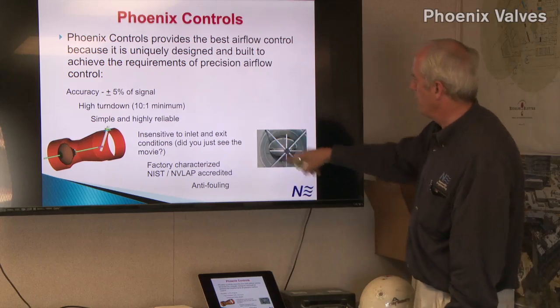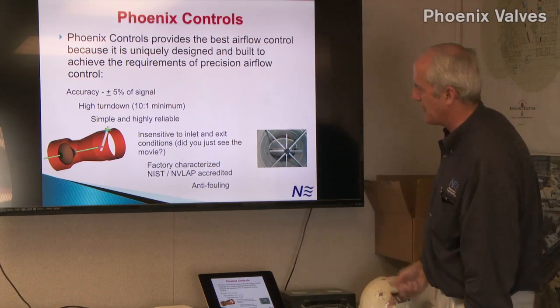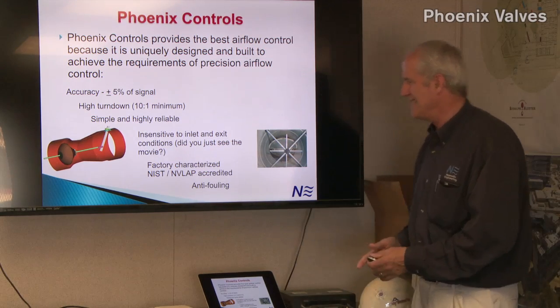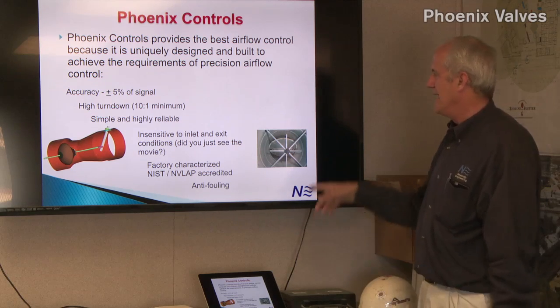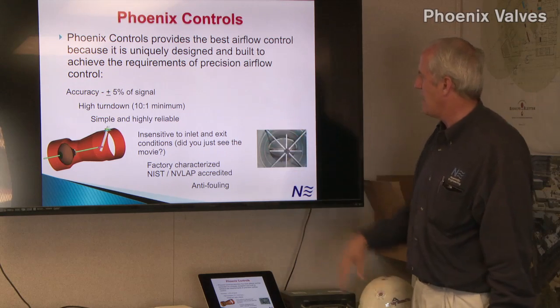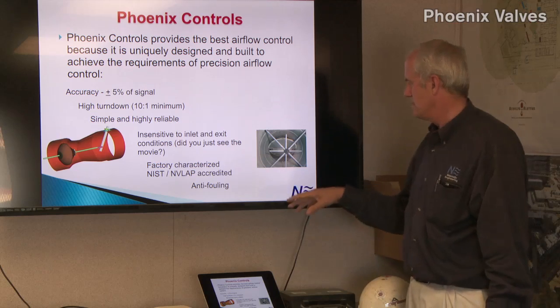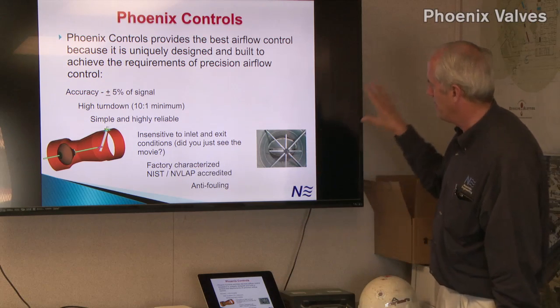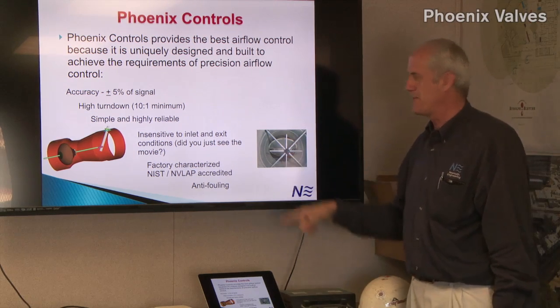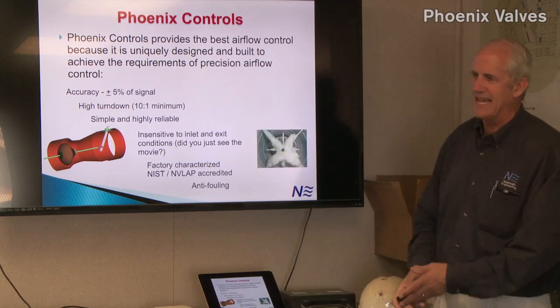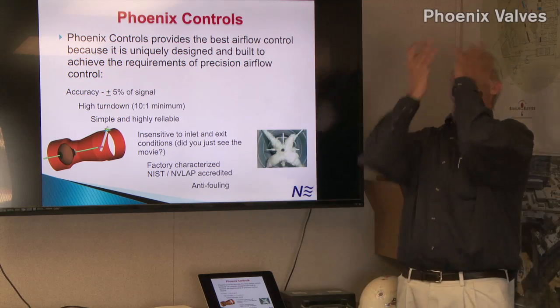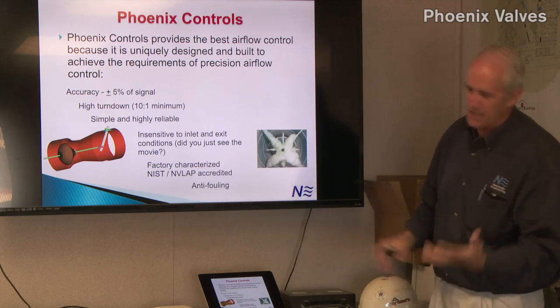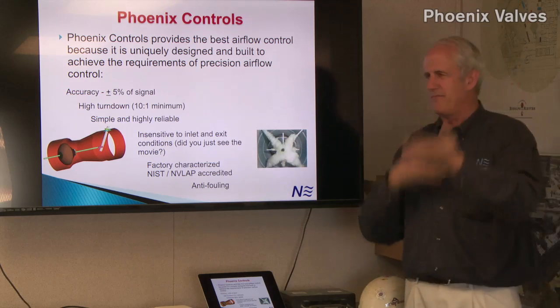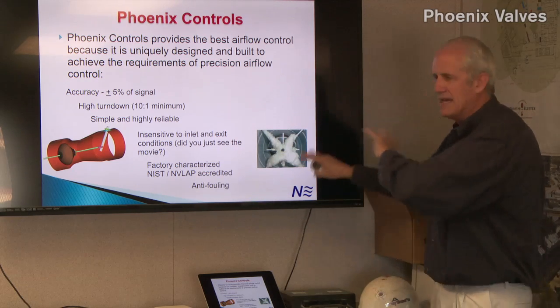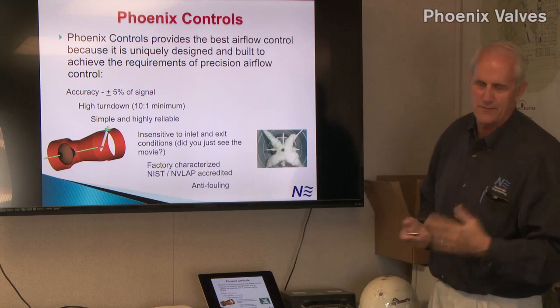Anti-fouling, and when you're measuring, this is what you have in front of a VAV box. We're on the medical campus, this was a VAV box in a hospital exhaust or return, I can't remember. 6 months later, they took a picture of that same device and it looks like that. So when you're measuring, the measuring can be fouled up. This happened to be lint, but in a vivarium, dander from the animals will do the same thing. It can really foul up your sensor. Your sensor stops reading back.